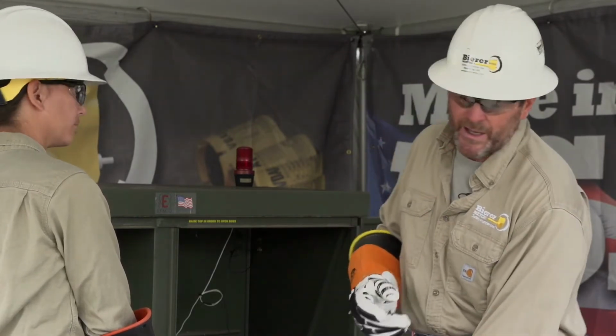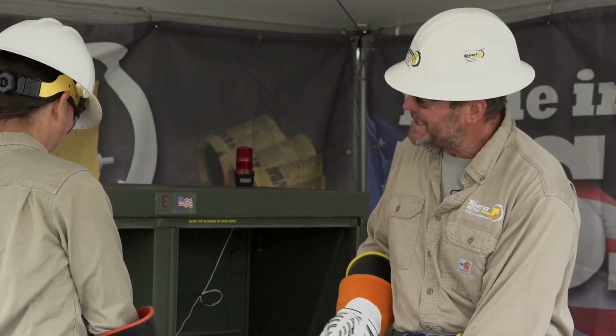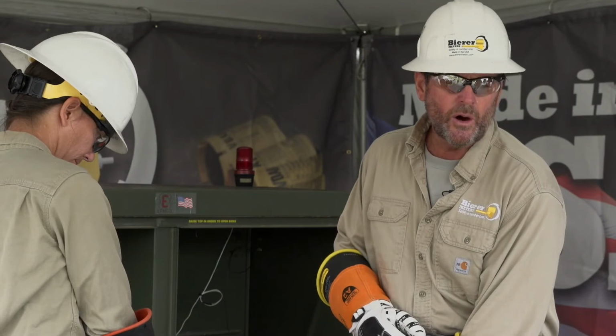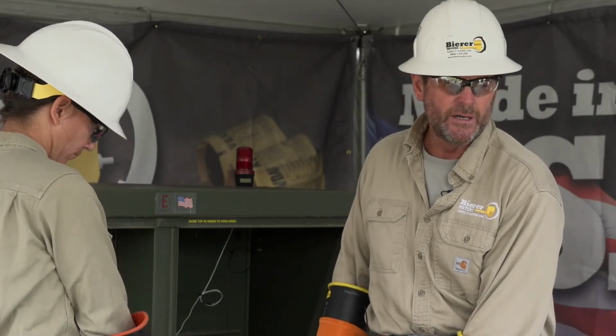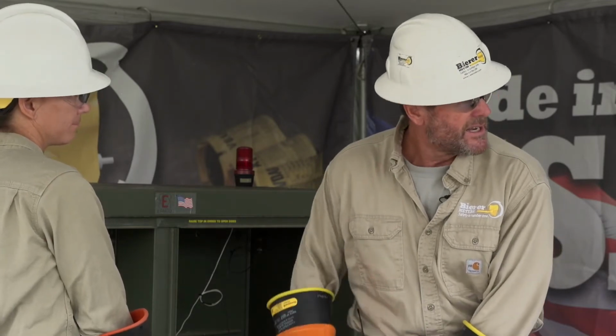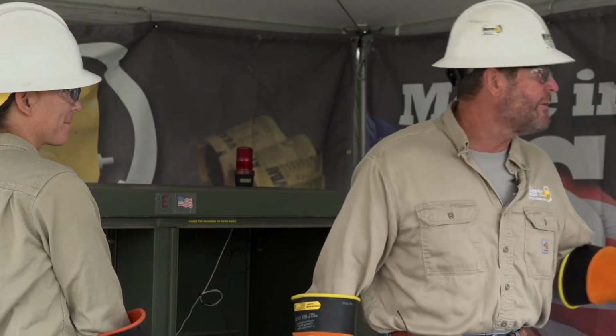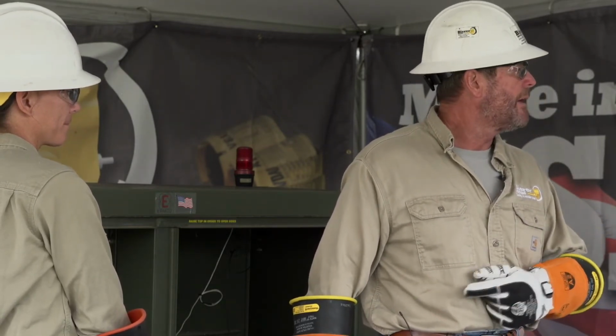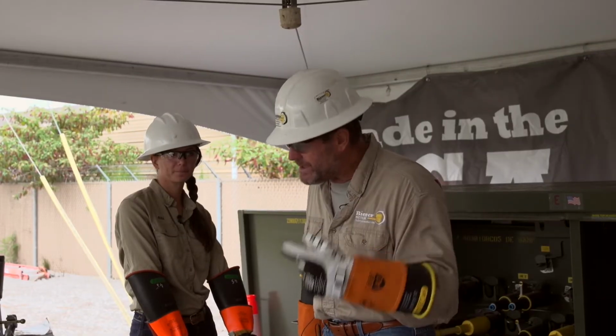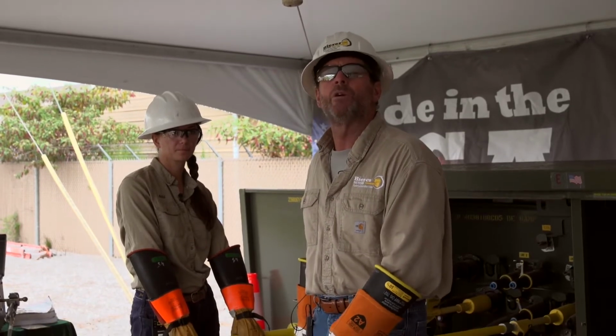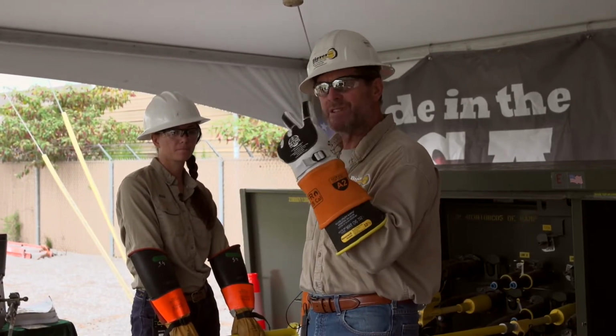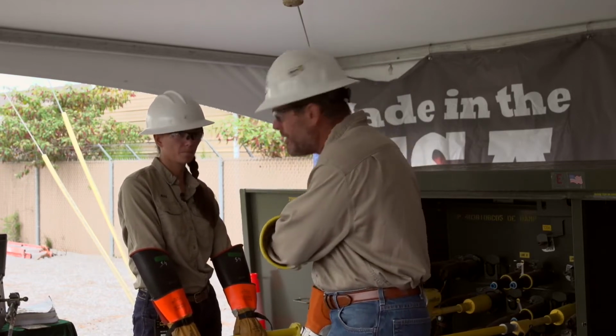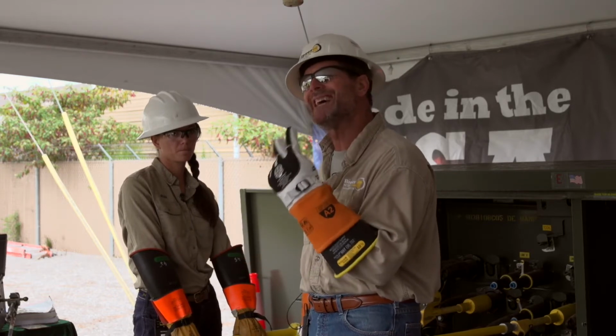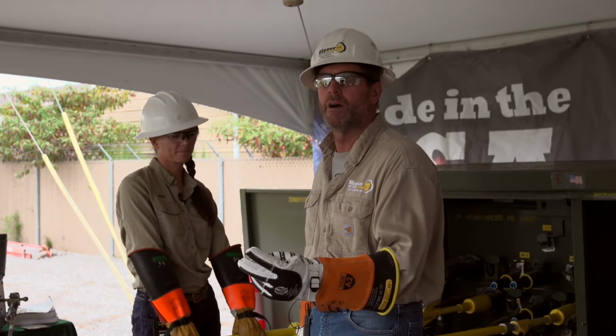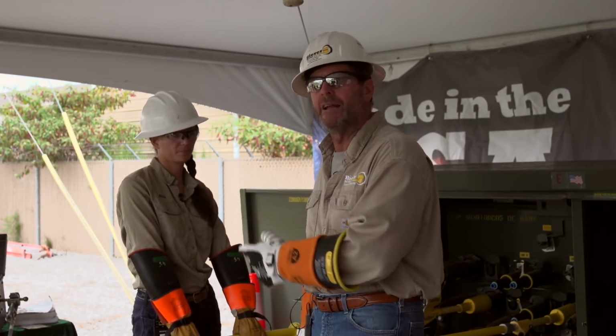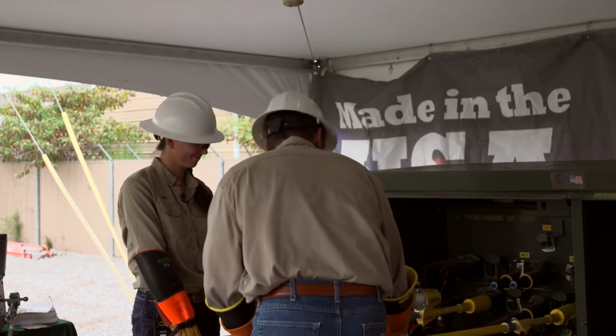Now, when we're done high potting, when we're done phasing, every single time what we're going to do is go with the secondary probe to ground first. Always. You don't have to do it in this sequence, but we're going to do it in this sequence, because we understand how these tools work and we're going to be extra safe. So we're always going to go to the secondary probe to ground first, and the reason why is because Abby wants to verify the tool is speaking to her, and when she takes the meter probe off that bushing, she wants the tool to tell her the device is de-energized. So it's more information - Abby likes a lot of information. So I'm going to go to ground first.